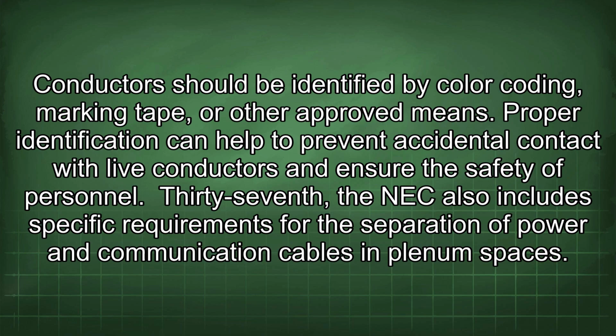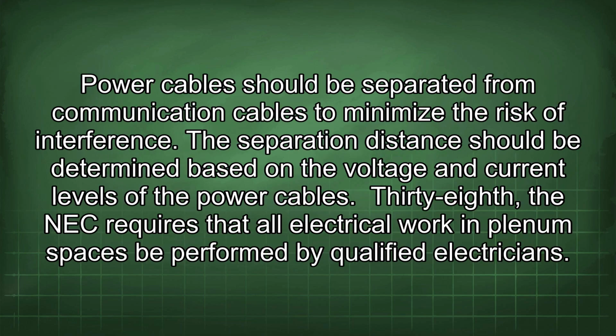37th, the NEC also includes specific requirements for the separation of power and communication cables in Plenum spaces. Power cables should be separated from communication cables to minimize the risk of interference. The separation distance should be determined based on the voltage and current levels of the power cables.